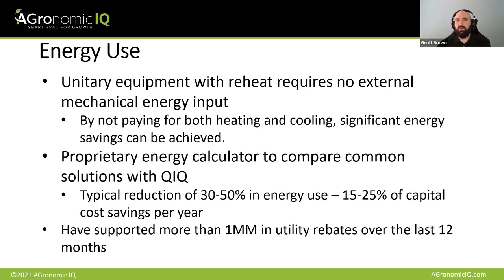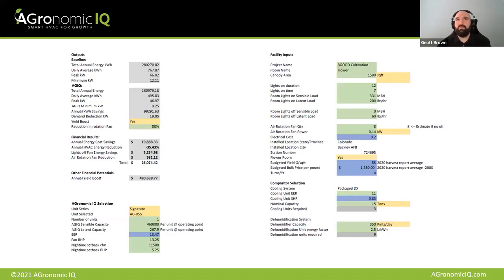Basically we produce an output that looks something like this. This is one we've done for a flower facility using Colorado, and this one's using Buckley Air Force Base in terms of weather data. We have a fair bit of calculation that goes on in the background, but you'll see that in general terms we're again between that 25 and 50% energy savings. This one happens to be about a 35% energy savings on an annualized basis.